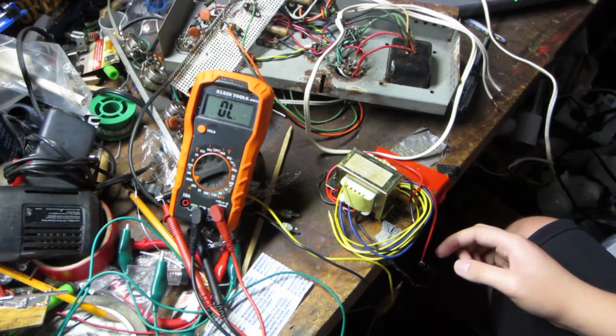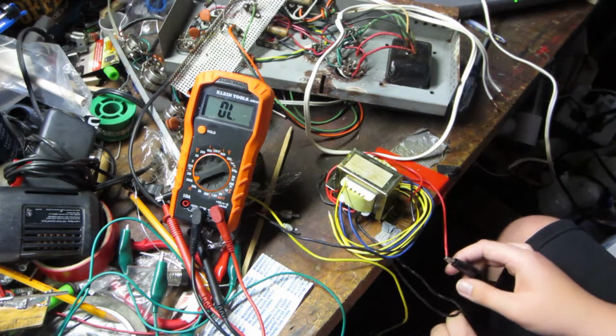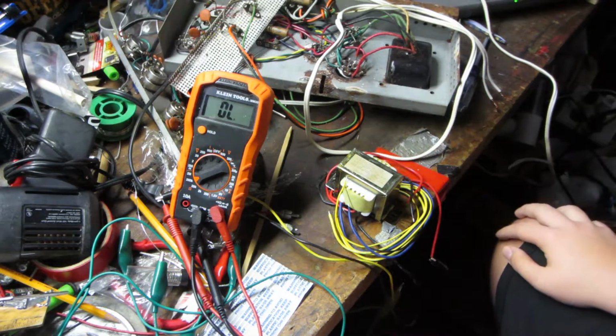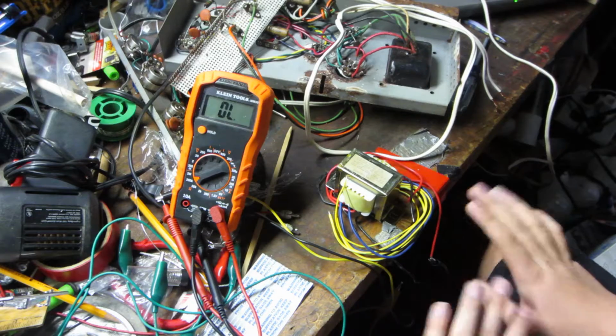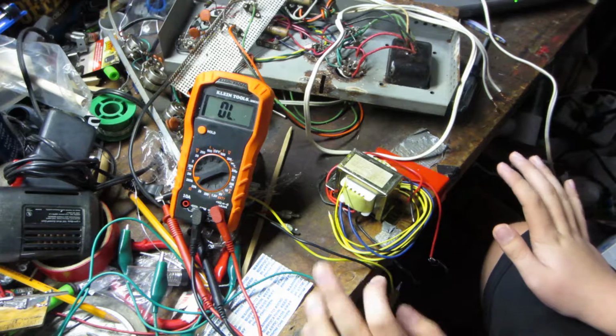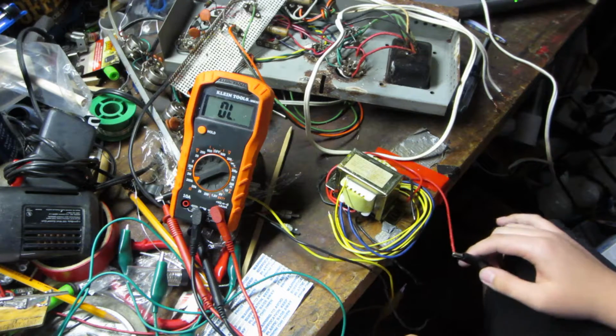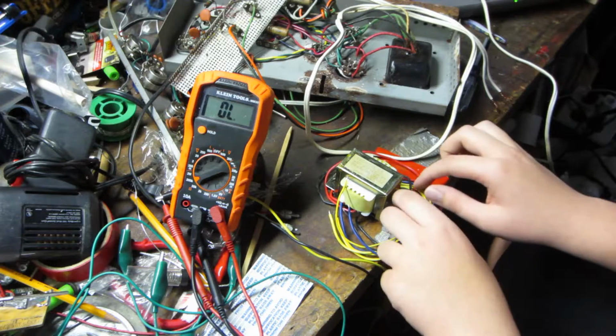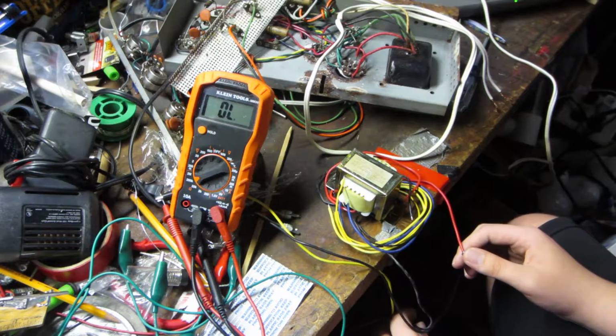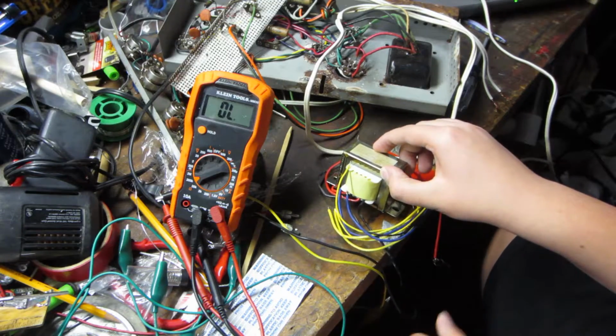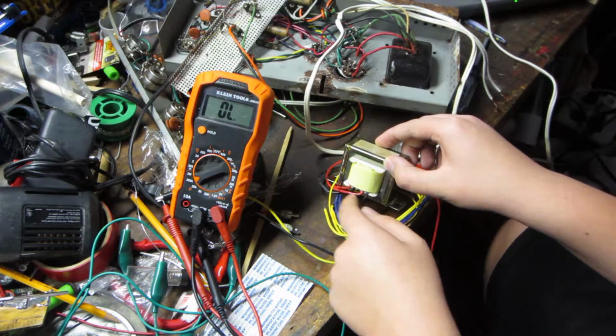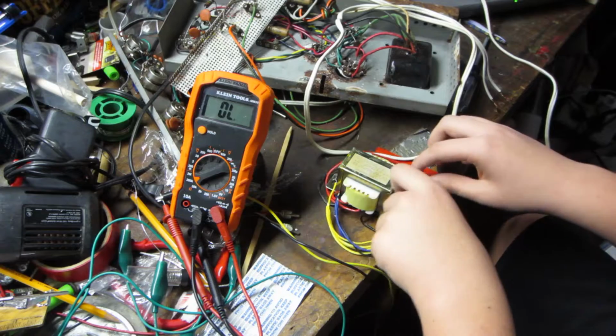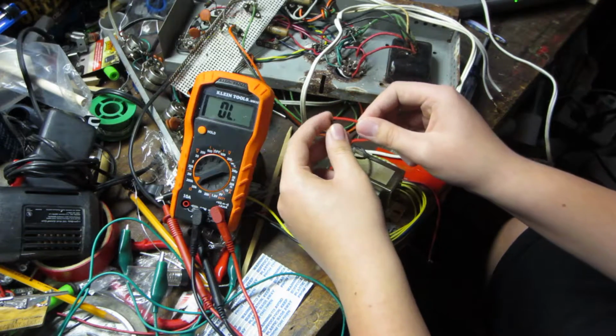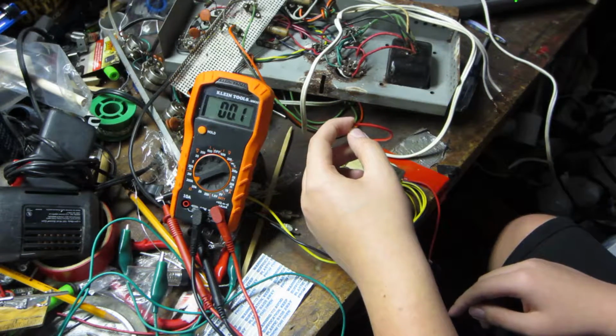So the two 115 volt input windings are completely separate. There are no center taps to it; they're just completely separate windings. And if you want to make 240 volts, you connect a wire to each end of the winding, like the black wire of one winding and the red wire of another winding, and then you take the extra ones here and touch them together, and that's how you get your 240 volt input.